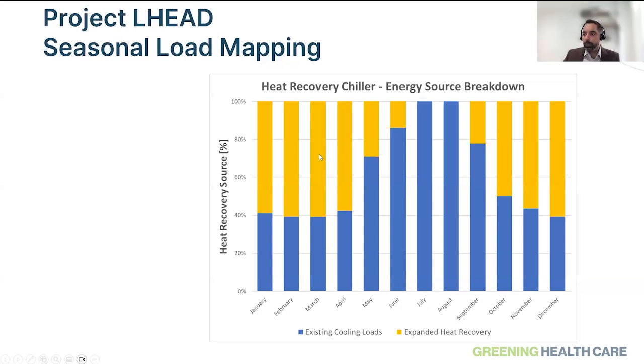Thanks, Darcy. And then this additional expanded heat recovery was a result of tying into or installing new exhaust heat recovery coils in those exhaust systems, right? Can you explain what that process was and how you accomplished that? Yeah, so we looked at a few different opportunities at Lake Ridge. We've done heat wheels, as you described earlier, on other projects. We looked at that, but what we found at Lake Ridge was a good opportunity where there was a single large exhaust system with an existing recovery coil in it, connected to a runaround loop to some air handling units. There was a large imbalance in the CFM in the exhaust and the units being fed. So we understood that there was additional heat to recover as a result of that. And so tying into that system was a relatively simple way to expand heat recovery through the winter.